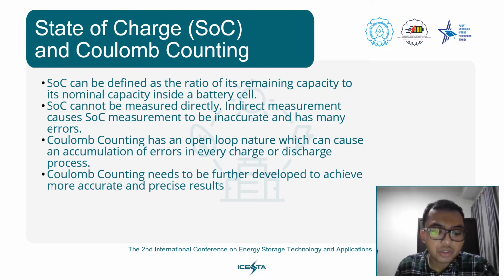To calculate or measure SOC, we cannot use direct measurement, but have to use indirect measurement by battery voltage and current. One of the methods to calculate or measure SOC is using the coulomb counting method. The coulomb counting method measures SOC by measuring the flow of current in and out of the battery, integrated over time. Besides being easy and simple, this method has weaknesses such as accumulation of error for each charge-discharge process.